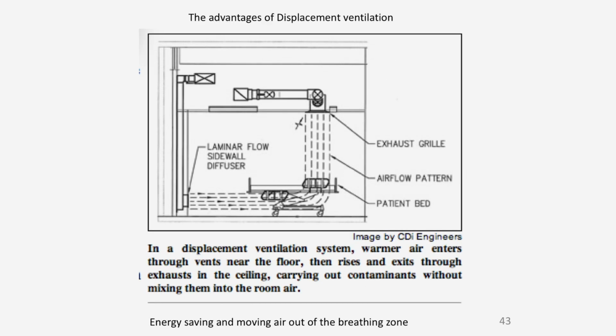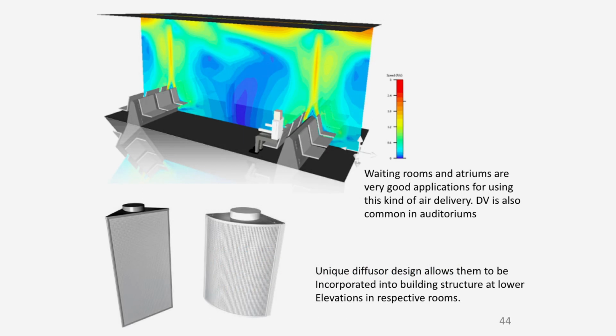And in slide 43, you can see a concept slide of air blowing in underneath the bed up to the ventilation system. And quite frankly, we feel that it's very hard to be able to do this because there's so little space in the walls that allow us to bring something down. So how do you bring that ductwork down and deliver it into that space? Hospitals are being built with dilution ventilation, but where I feel displacement ventilation has its big advantages is in waiting rooms and atriums.